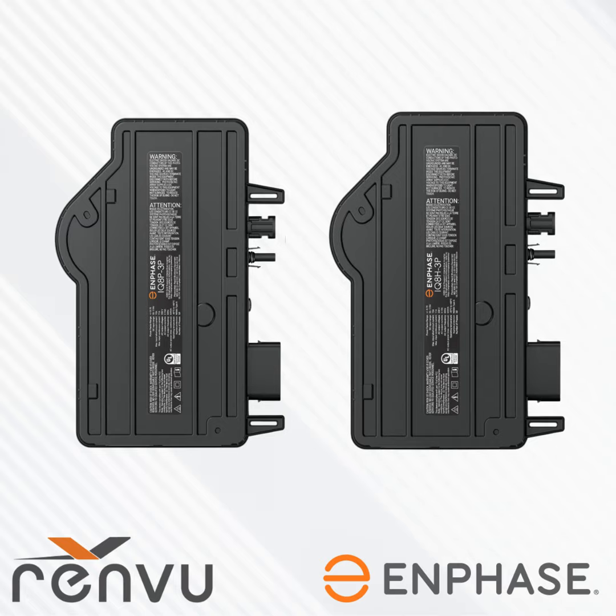So designing with this system, I just want to skip forward. Designing with this system is very easy, but there's a few limiting factors. One limiting factor is the number 12 conductors inside of that Q cable, and the other one is this commercial gateway. Your commercial gateway is going to be able to talk to 275 microinverters at a max distance of 240 feet. So what that means is the maximum amount of commercial microinverters per gateway is 23 branch circuits of IQ8P and 18 branch circuits of IQ8H. Again, that's roughly 130 kilowatts for 8P and 105 kilowatts for 8H on a single gateway.